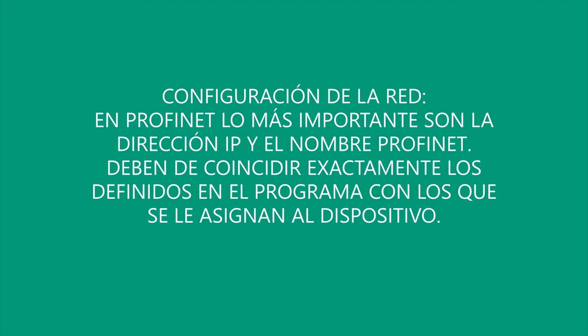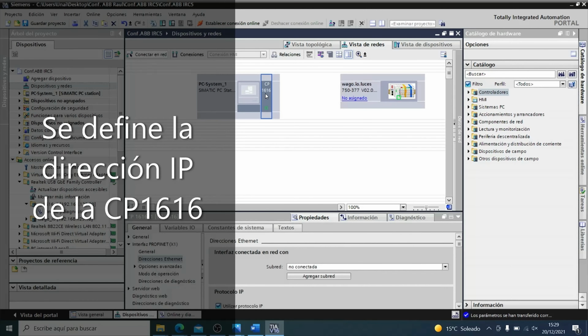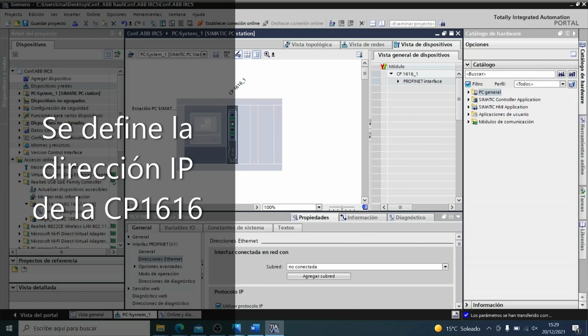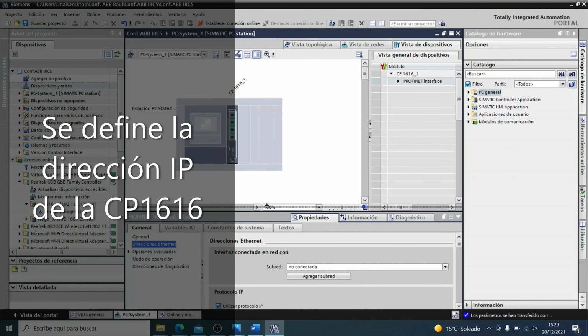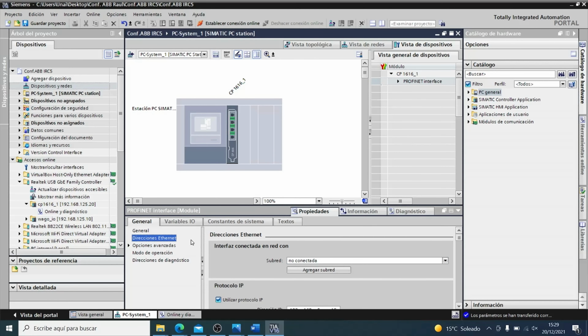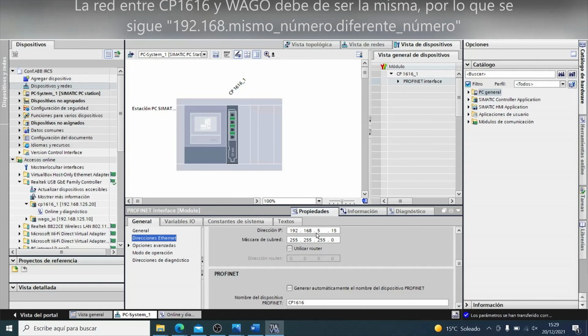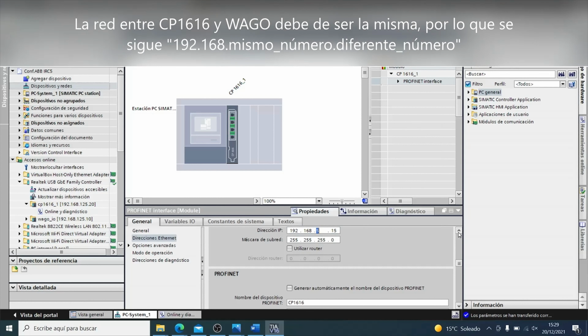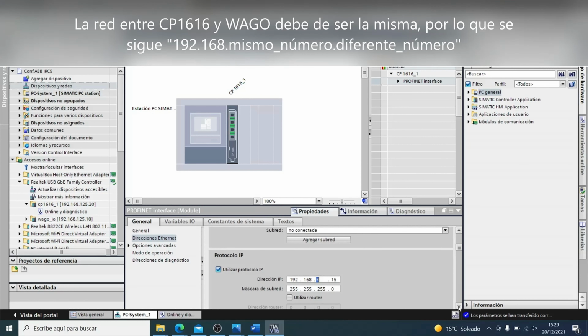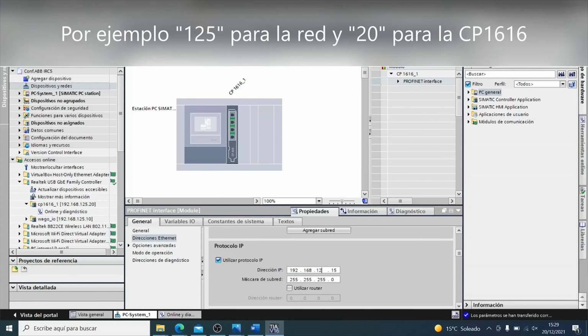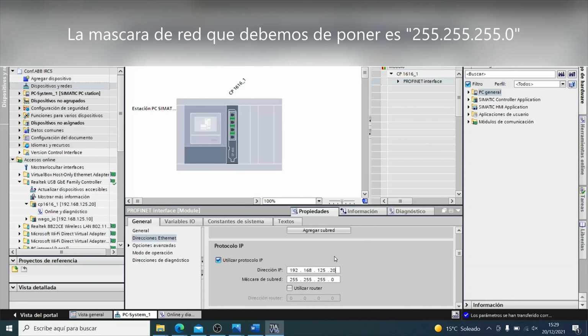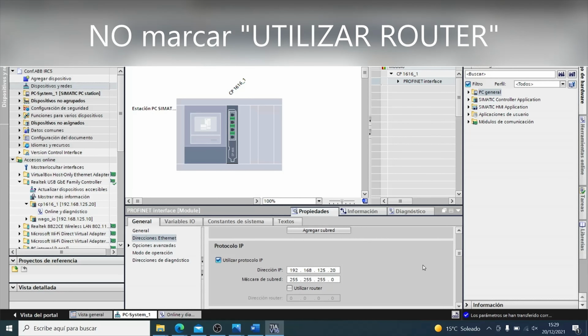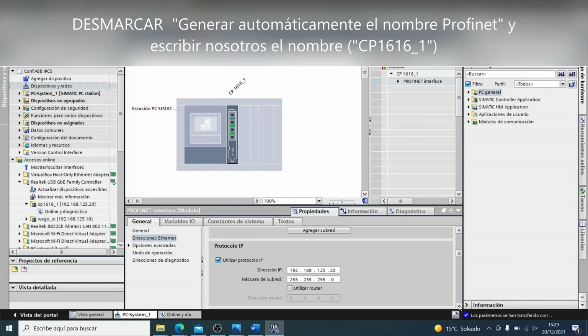Two of the most important things are the name and the IP address. The name has to be the one that you assign in the project to the device and has to be the same one as the device. Here I will assign the IP address in my network and then the name in the PROFINET network. You can see right now the project assigned 192.168.5.15. The last few numbers we can change to put them in the same network we have. Right now, for example, 125, and then the device will be number 20.